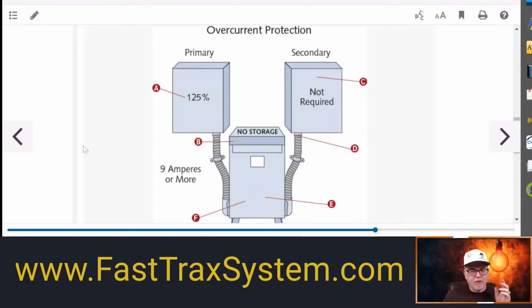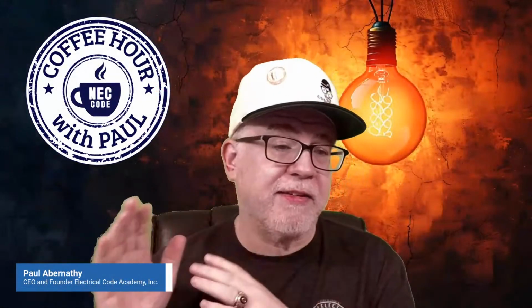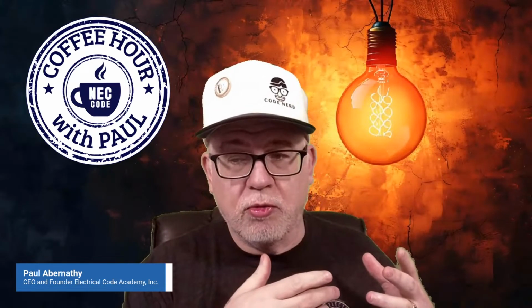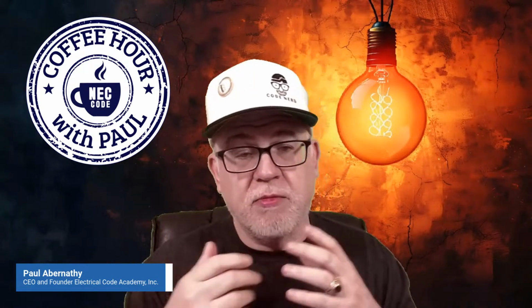Now, one of the things I do want to bring up for folks, just as a topic of discussion, and let this bounce around in your head, is that sometimes you have to remember that these conductors right here are going to be exposed to loads on the secondary that are continuous loads. So you'll have continuous loads, and then you'll have non-continuous loads. So in order to make sure that you're sizing these conductors properly, now if you size everything in the transformer to 125, then you're not going to go wrong, okay? And if you're in the real world, that's probably what you're going to do, because again, we still can't be less than the primary protection, right? So you'll be okay. But I always tell engineers, any engineers that are listening out there that are designing systems, to remember that in many cases you could have loads on that secondary that are going to transfer over to the primary side, and you might have continuous loads, and then you might have non-continuous loads.